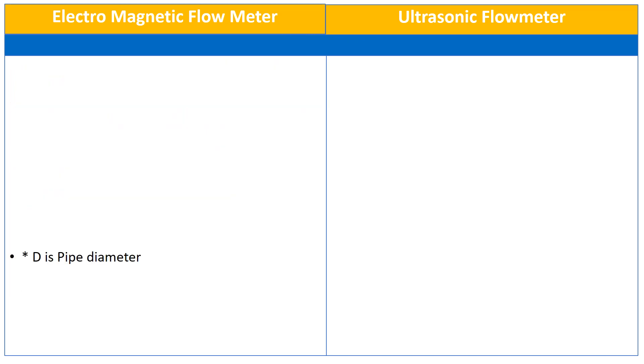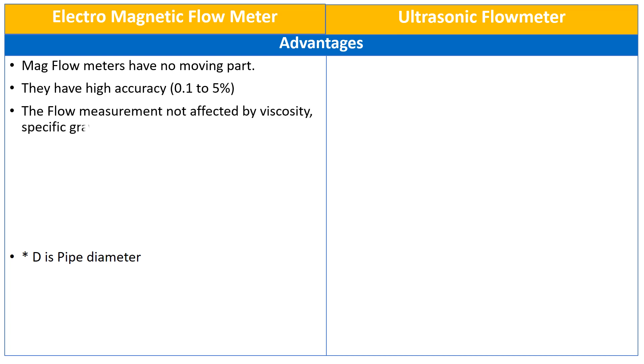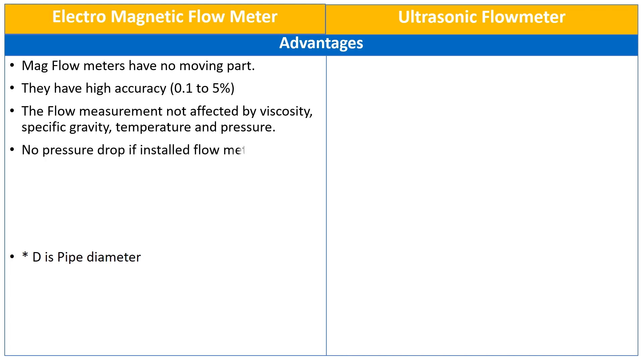Let us see the advantages of electromagnetic and ultrasonic flow meters. In case of electromagnetic flow meters, they have no moving parts, so very less maintenance is required. They have high accuracy of 0.1% to 5%. The flow measurement is not affected by the viscosity, specific gravity, temperature, and pressure of the fluid. There is no pressure drop if the installed flow meter is the same size as the pipe size.